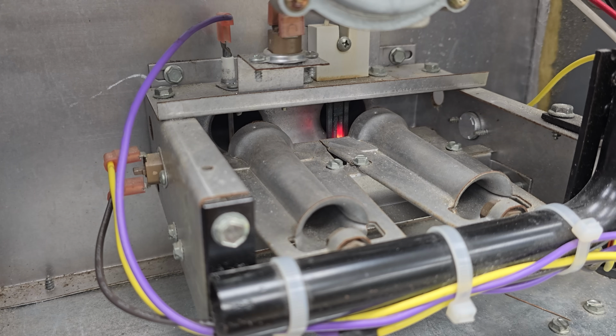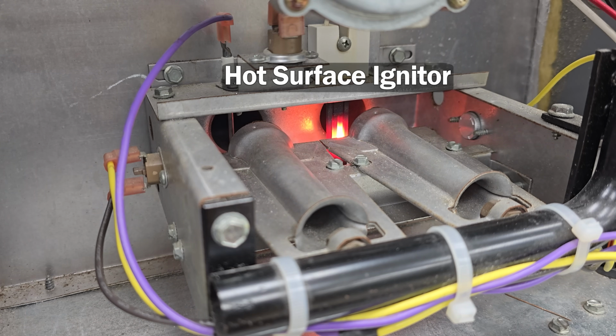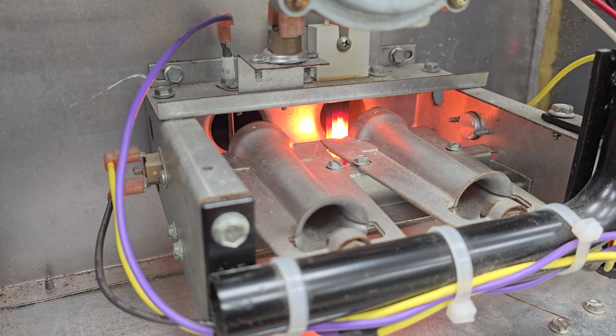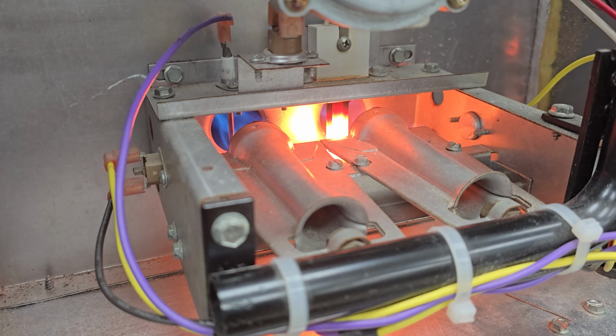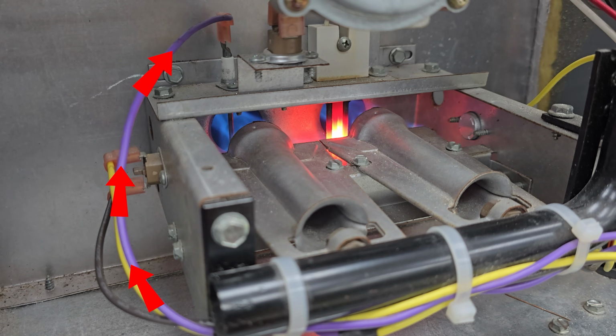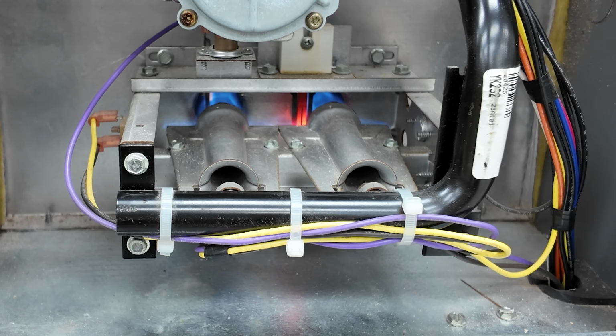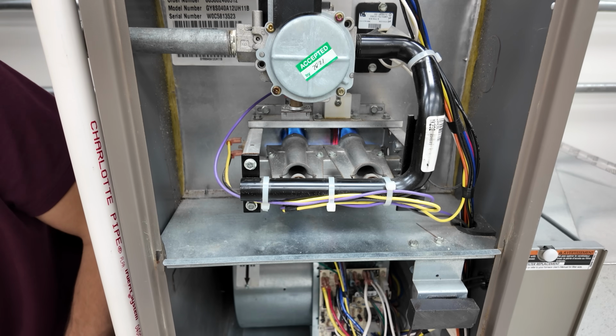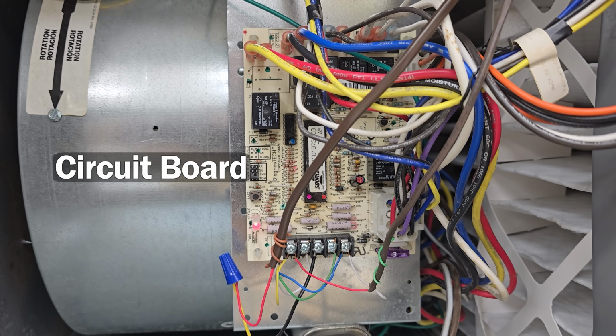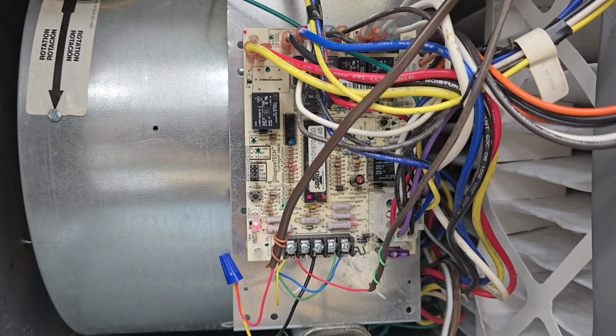If you can see inside of here, there's a hot surface igniter, and that's turning cherry red. After that gets very cherry red, we're going to have the full gas flow going into the burner area, and so you're going to have ignition. Over here on the purple wire, you have the flame rod, and that's proving that you have a flame. Then you come down to this circuit board, and the circuit board understands that the flame is there, and it has a blower on delay, which means that the heat exchanger needs to warm up before the blower motor turns on and circulates that hot air through the building. So we're in that initial maybe 20 seconds, 30 seconds, and now the blower motor has turned on.